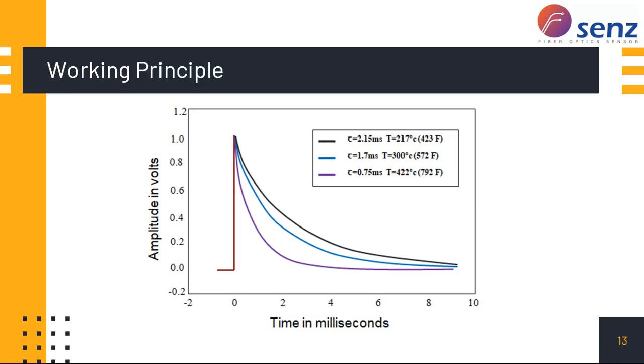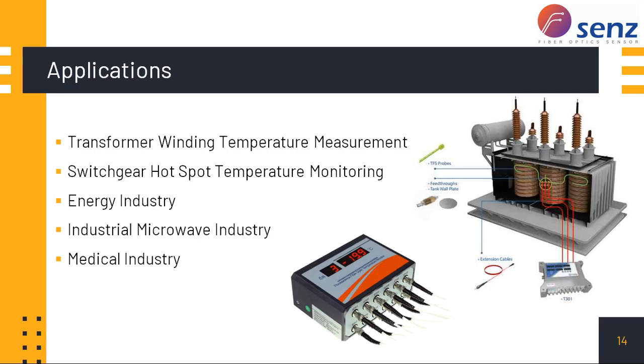With a special algorithm, we can find out the decay rate, which is proportional to the temperature, and we can find out the temperature by this method. So this technology is used for multiple purposes, but the major use of this technology is for transformers of more than 30 MVA. Fiber optic sensors are being used in the industry as a standard.